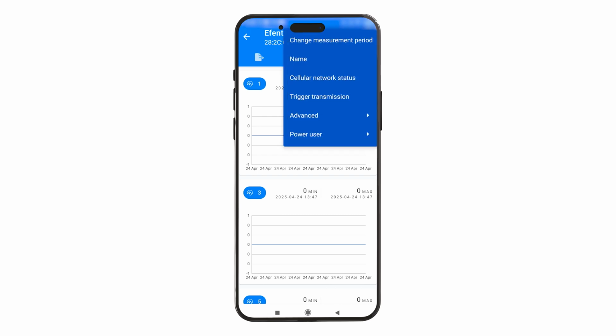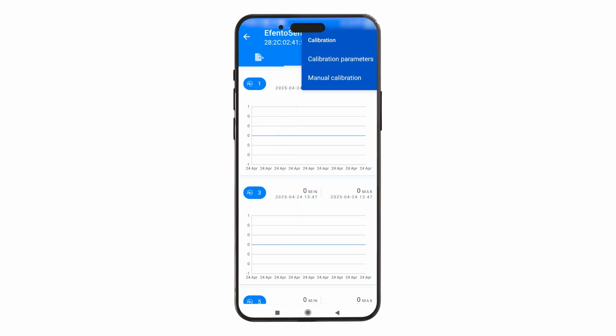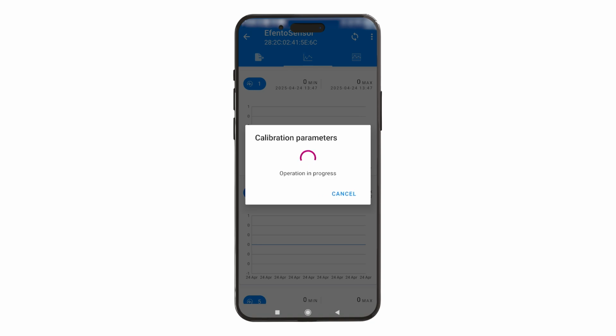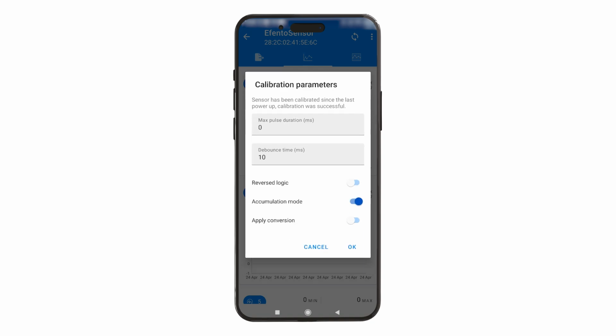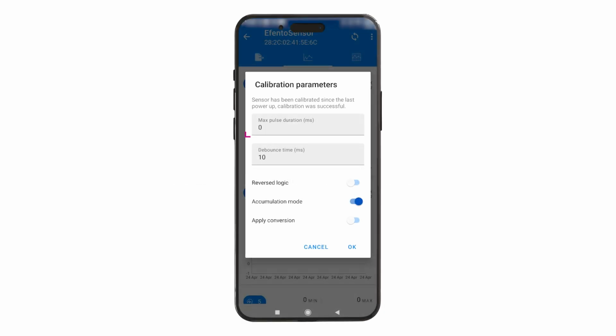If the manual calibration was successful, you can proceed to adjust the device settings according to your preferences. Reconnect to the sensor and go to the calibration window. The adjustable parameters are: Maximum pulse duration defines the maximum duration of a pulse. If the counter receives a pulse that exceeds the time set in this parameter, it will display an error. This parameter helps monitor the correctness of pulses generated by, among others, utility meters equipped with pulse outputs of defined pulse durations. By default, the pulse duration control is disabled, and the sensor treats every pulse as acceptable.